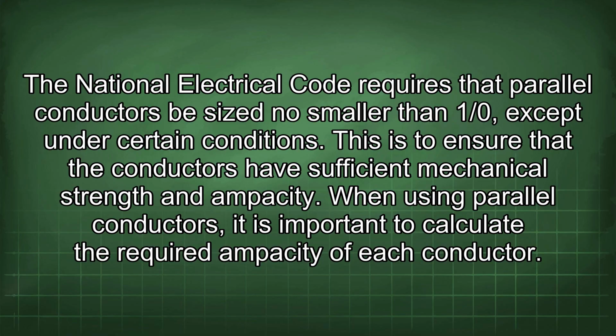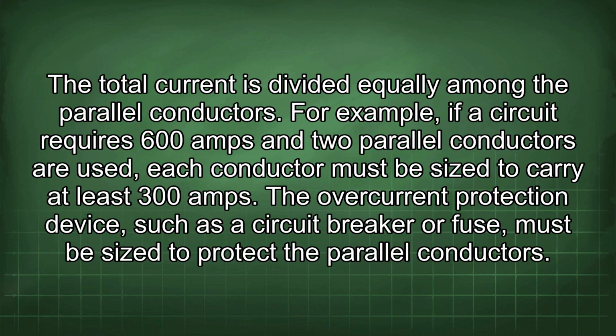When using parallel conductors, it is important to calculate the required ampacity of each conductor. The total current is divided equally among the parallel conductors. For example, if a circuit requires 600 amps and two parallel conductors are used, each conductor must be sized to carry at least 300 amps.